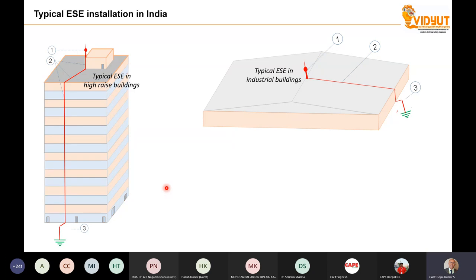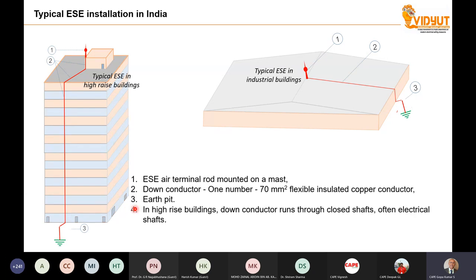Why an insulated conductor? Because people say that, because of the insulation, the current will go through the conductor without damaging the nearby things. So insulated down conductors are used. And there is one earth pit. So mostly the promoters of such systems say this is a very simple system. One rod, one down conductor and one earth pit, and all your problems are gone. Also for industrial installations, imagine there is a large industry; at the top of the building there is a rod, a down conductor and an earth electrode.